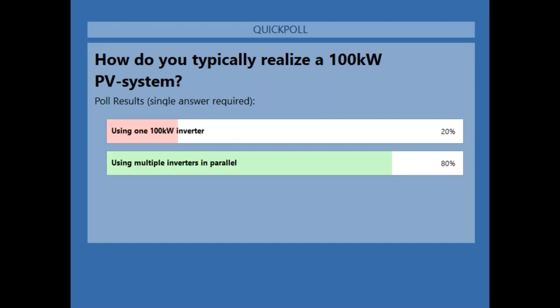So a lot of today's attendees still prefer to compose a 100 kilowatt PV system using multiple inverters in parallel. This is actually a smart move, because if you have one single 100 kilowatt inverter and there's an issue with it, your total system is down. Whereas if you have 3 or 4 inverters in parallel, and there's an issue with one of them, your other inverters are still operating and the system can still almost be at its full capability. Again, from Fronius, for any system less than 100 kilowatts we suggest you still use the Fronius Symo and the Fronius Eco, and for any system greater than 100 kilowatts, you now start to look at the Fronius Tauro.